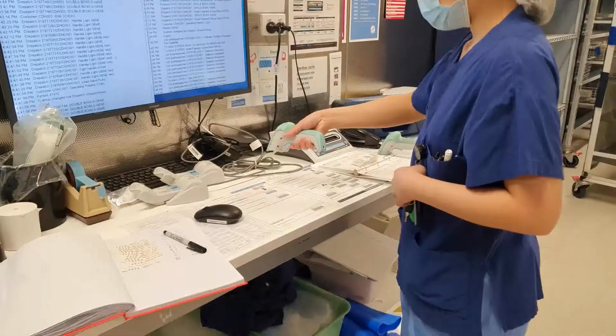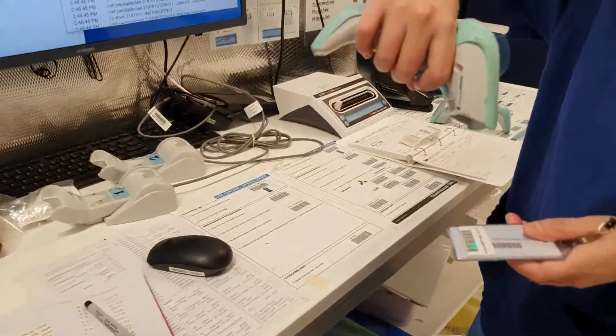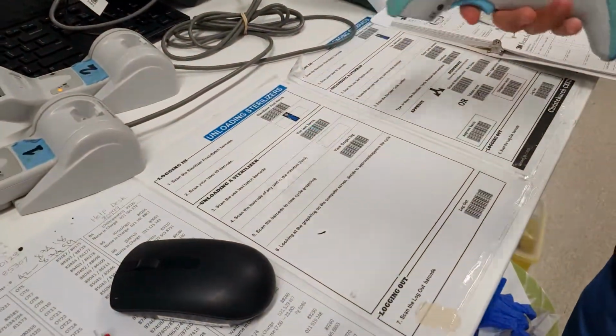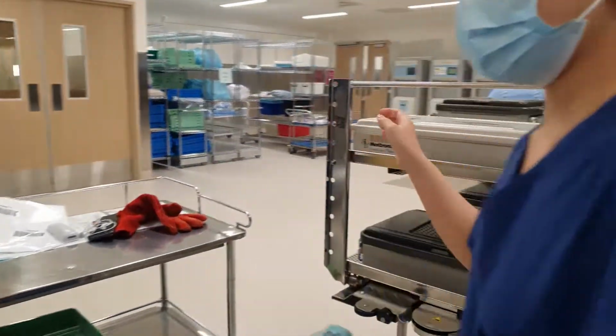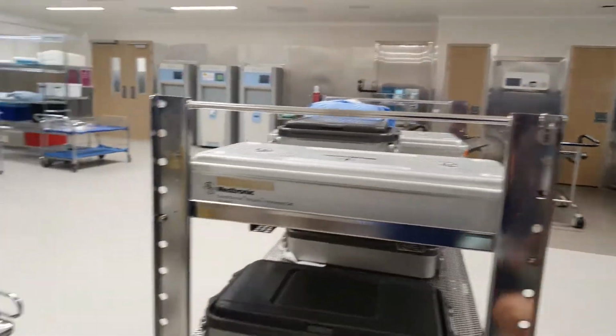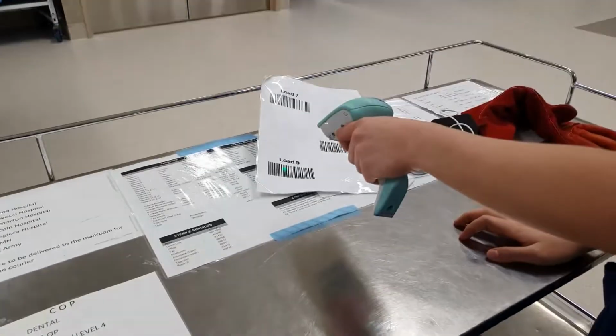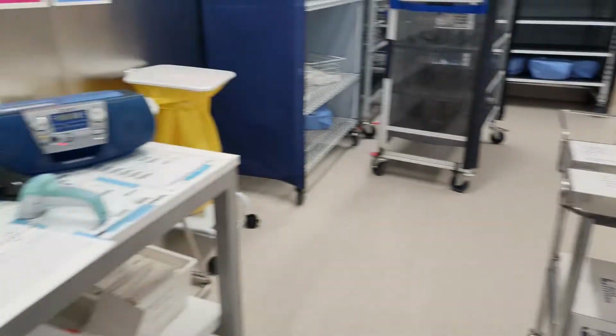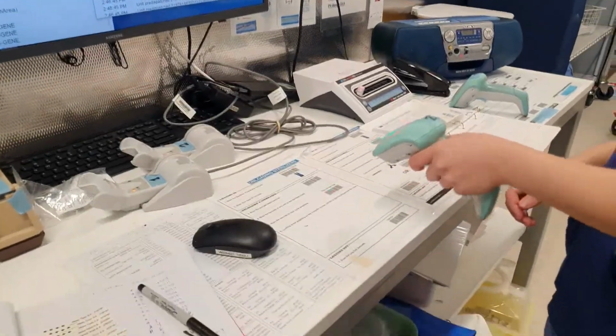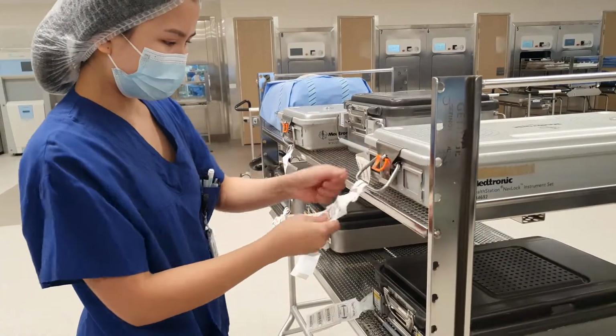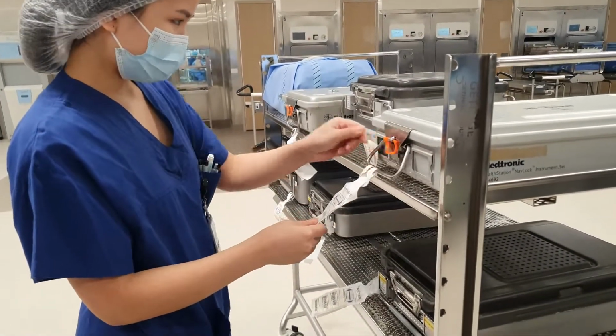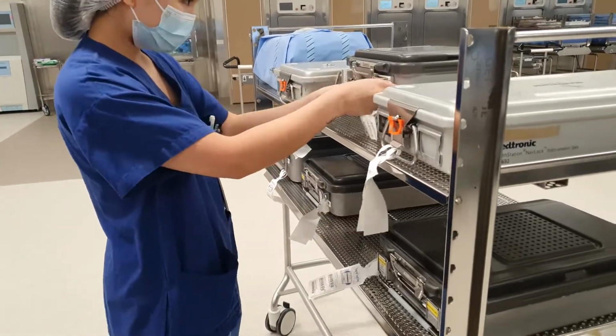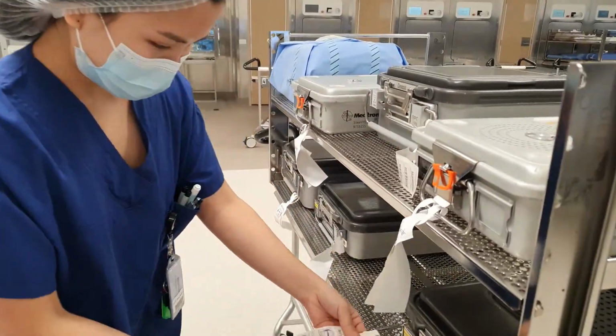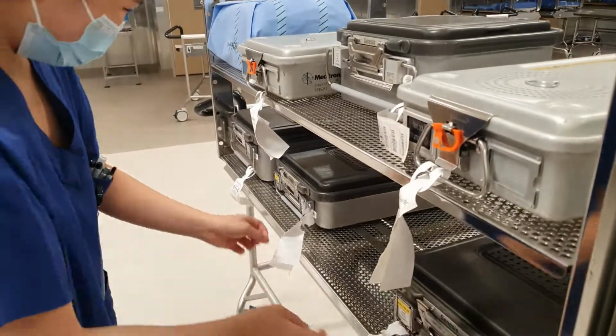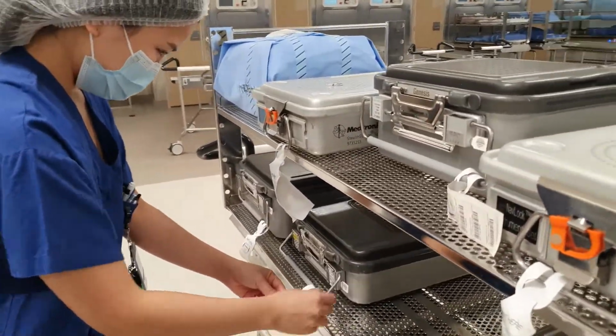Instrument sets and other reusable medical devices must remain on the sterilizing trolley until adequate cool-down time and can be handled safely by the operator. Also, it is vital not to touch instruments before they have cooled, as packages still contain a significant amount of moisture after being exposed to steam. The moist area can draw bacteria from our hands into the package and would compromise its sterility. A minimum cooling time of 30 minutes is recommended.